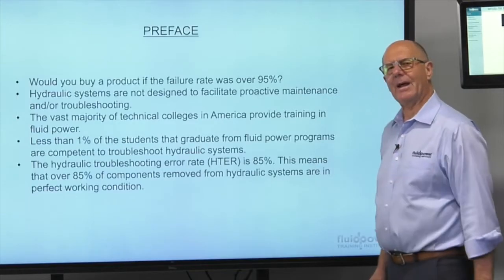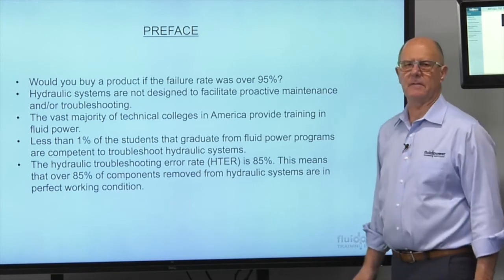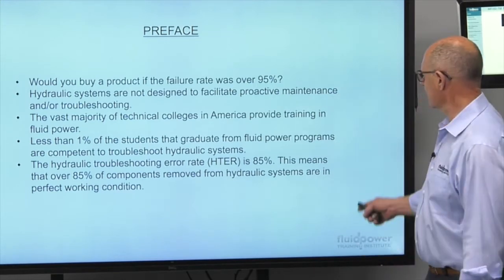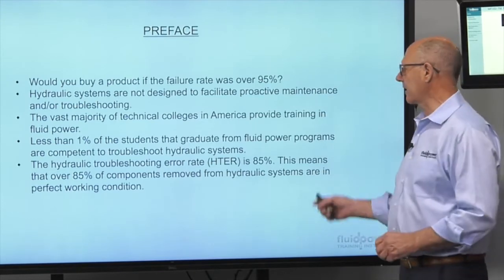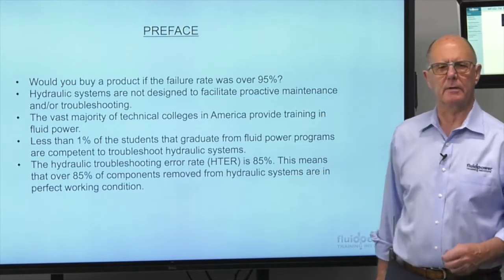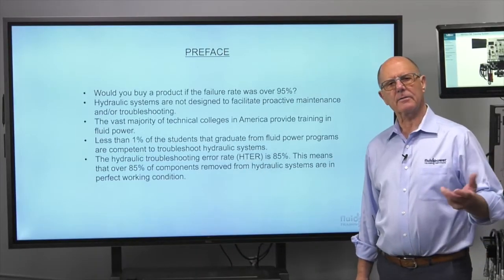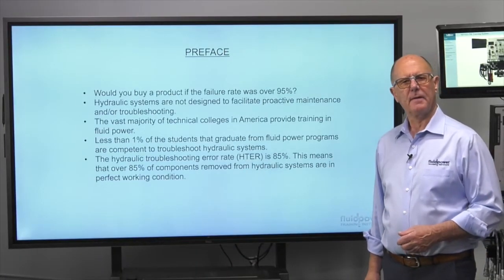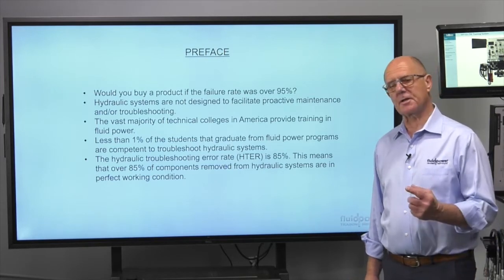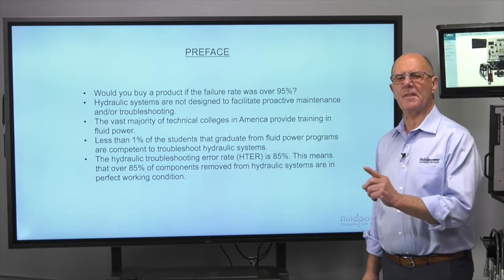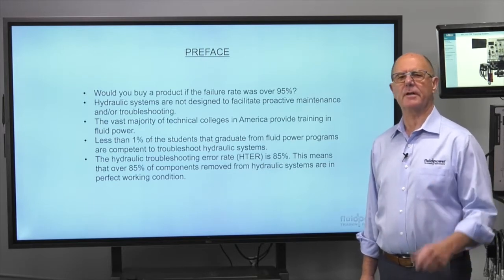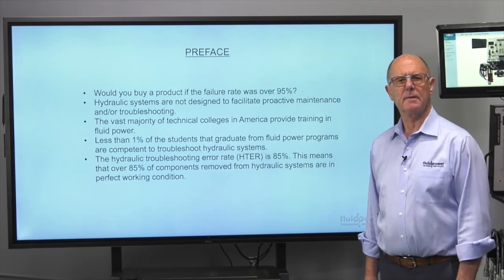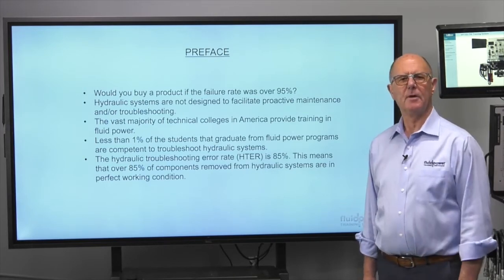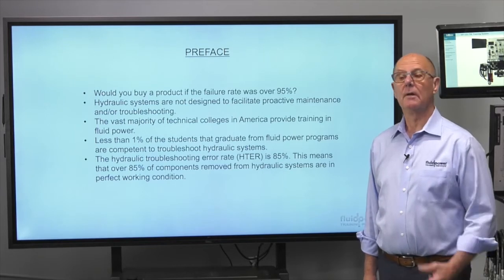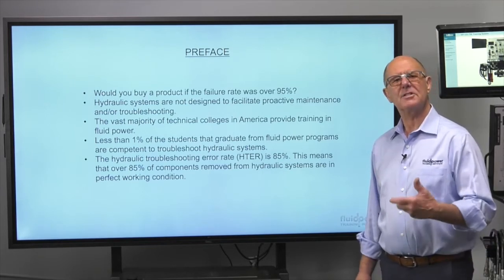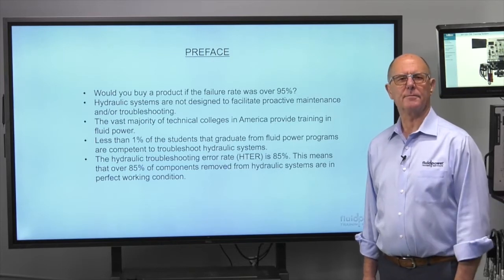The hydraulic troubleshooting error rate, I call it the HTER, is 85%. That's a conservative estimate. This means that over 85% of the components removed from hydraulic systems are in perfect working condition. I had a client recently call me from a mine in Nevada that had a problem on a hydraulic system which cost them ultimately $167,000 to fix. They replaced every hydraulic component on the machine. It's disgraceful. It was an elementary problem. They have good, hard-working technicians. They just don't have the skill set to find the problems.